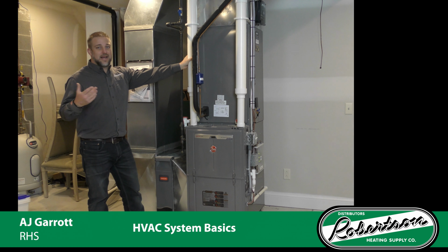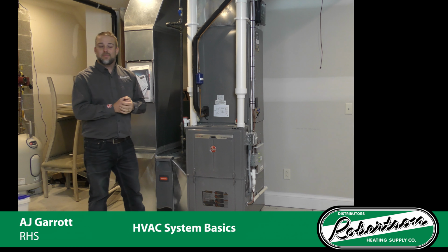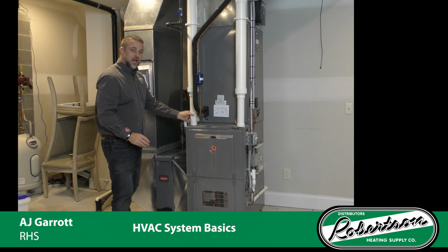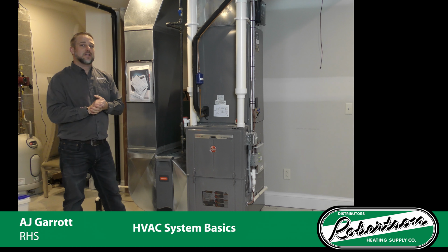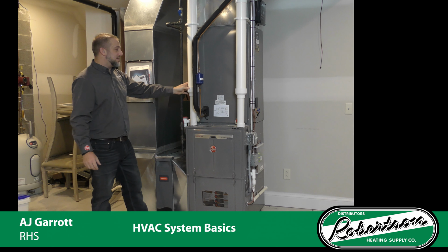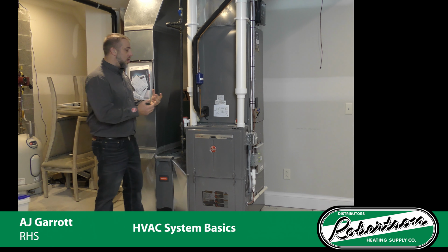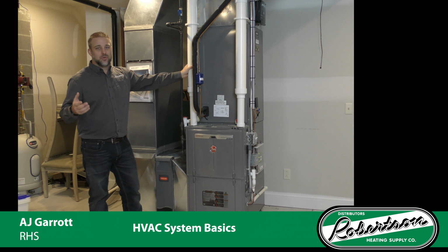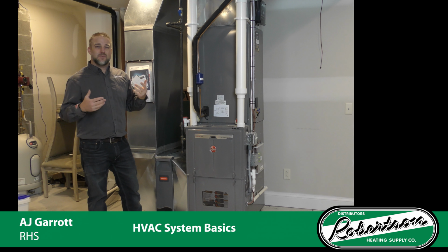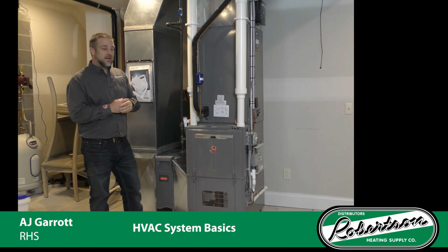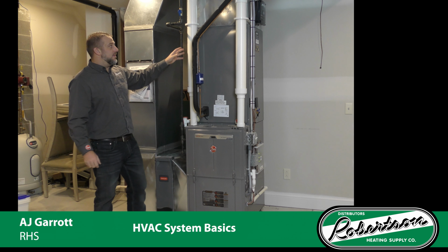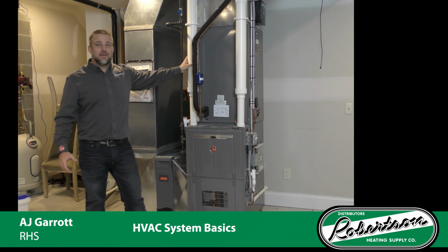Now, what do we do with that gas and that flame and all the particles of combustion? We send that out the chimney. So here is actually the exhaust pipe. This is a 96% efficient gas furnace. So the reason it's vented in a PVC plastic pipe is because it actually condenses and it's a lower temperature. So the temperature of a typical 95% or 96% gas furnace is probably somewhere around the 105 to 110 degree range. When we get down to those cool exhaust temperatures, they start to condense. That's why we have to have it in a plastic PVC pipe.